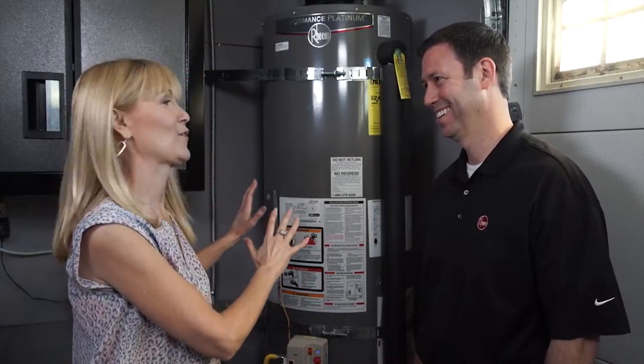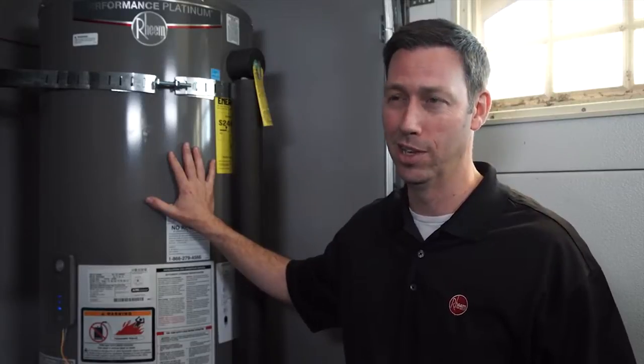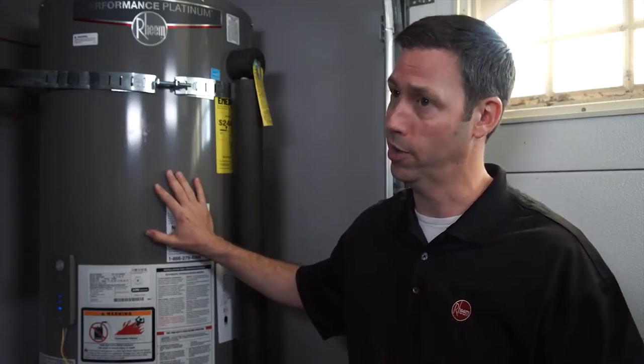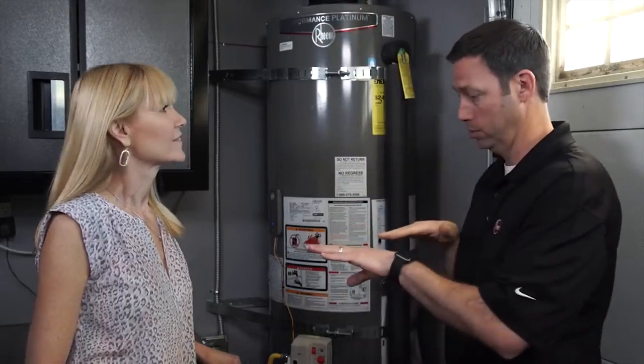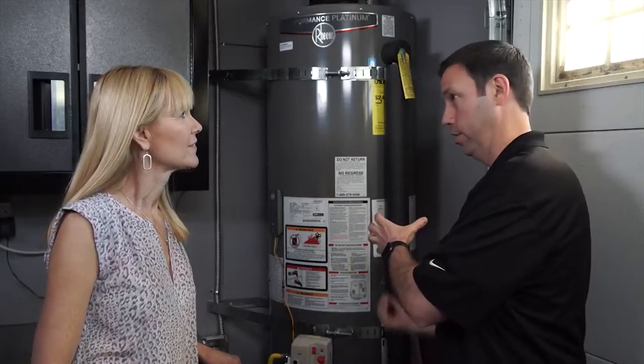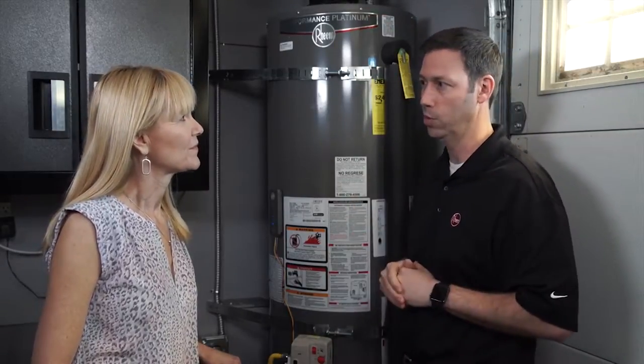Can you tell us in general what's happened with water heaters in the last five or ten years? So in this house, this model replaced a 30-year-old unit, so we've got a giant leap forward in efficiency. But don't forget, water heater codes have changed in the last couple of years, so this model, even if it were replacing a five-year-old unit, is going to be quite a bit more efficient. It's got a power damper up here — basically a damper that closes over the flue. As this unit is burning gas and making hot water, flue gases run up through that flue, and when the burner shuts off, it throws a damper over the top to keep the heat in and capture a little bit more of that heat.